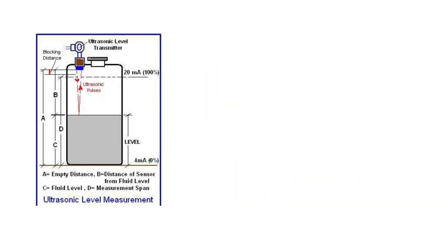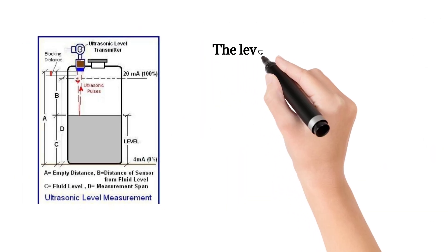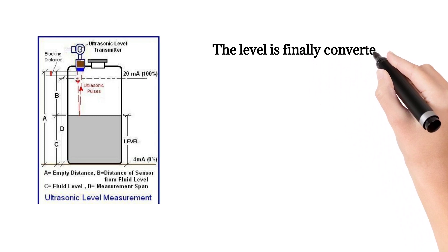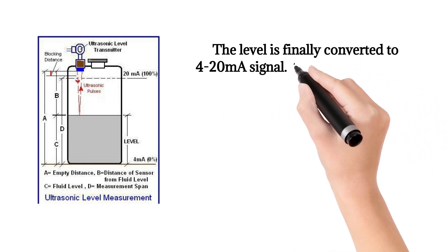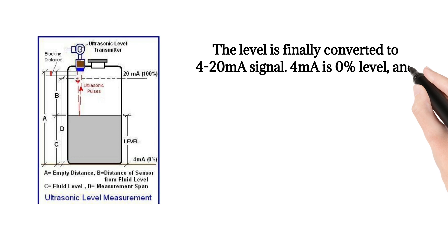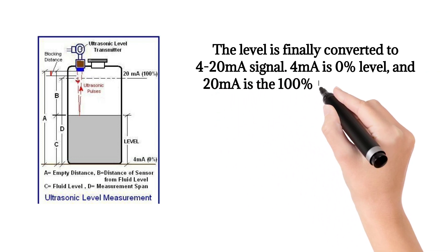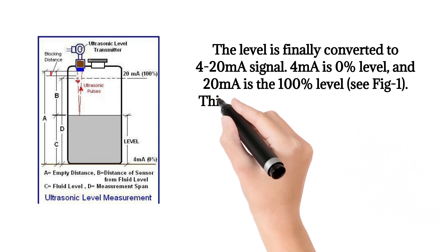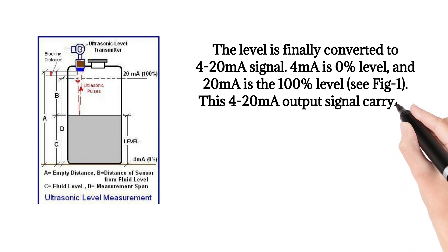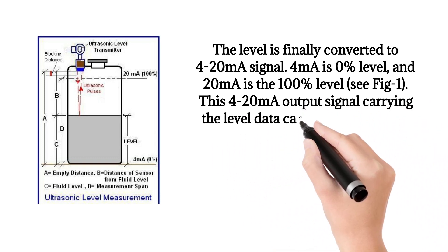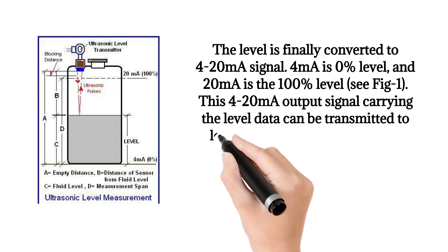The level is finally converted to 4 to 20 mA signal. 4 mA is 0% level, and 20 mA is the 100% level. See Figure 1. This 4 to 20 mA output signal carrying the level data can be transmitted to long distances to process control instruments.